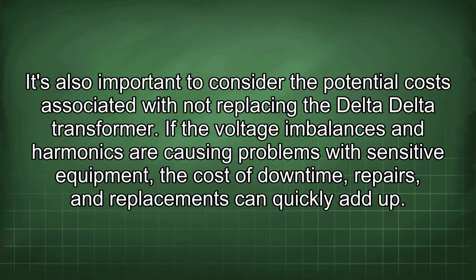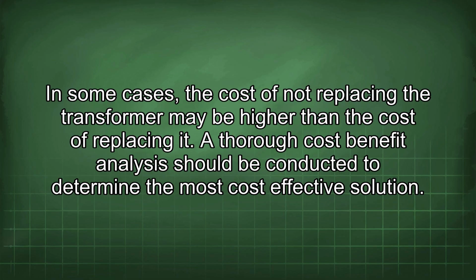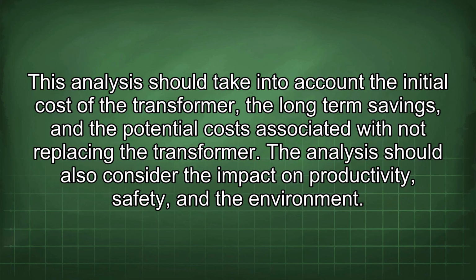It's also important to consider the potential cost associated with not replacing the Delta-Delta transformer. If the voltage imbalances and harmonics are causing problems with sensitive equipment, the cost of downtime, repairs, and replacements can quickly add up. In some cases, the cost of not replacing the transformer may be higher than the cost of replacing it. A thorough cost-benefit analysis should be conducted to determine the most cost-effective solution. This analysis should take into account the initial cost of the transformer, the long-term savings, and the potential costs associated with not replacing the transformer. The analysis should also consider the impact on productivity, safety, and the environment.